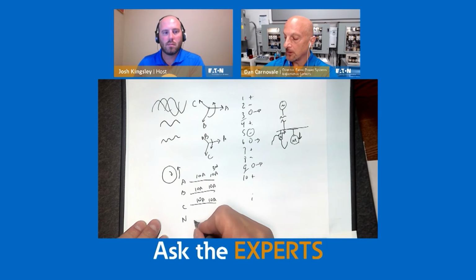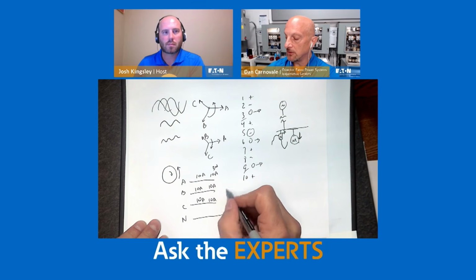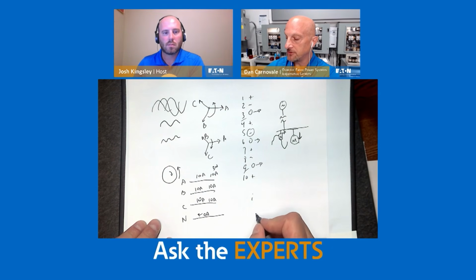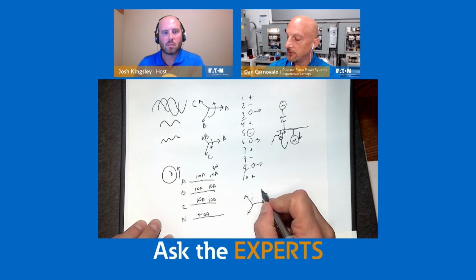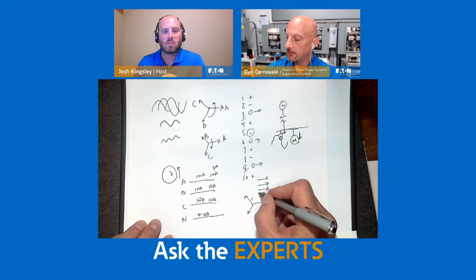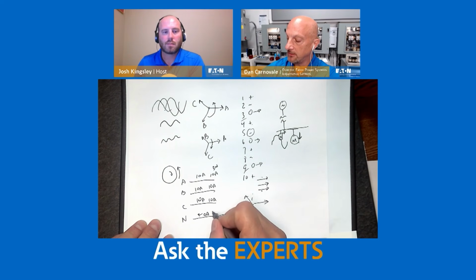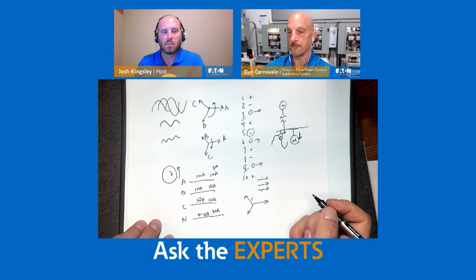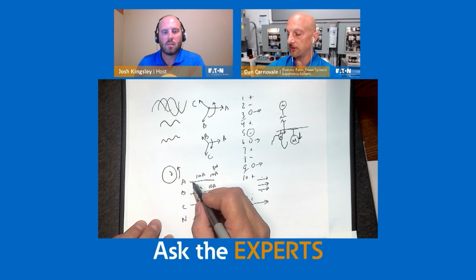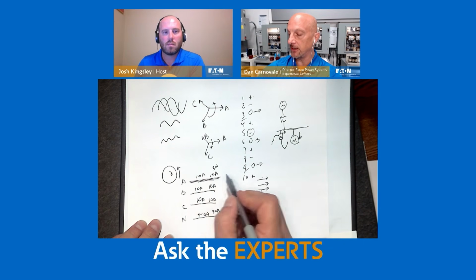multiples of the third. So third, ninth; sixth isn't usually very common. But anyway, what we would have on the neutral out here is 0 amps of 60 hertz. As we mentioned before, 60 hertz A, B, C adds up to 0. But the third harmonics, A, B, C, 10 plus 10 plus 10, is going to add up to 30 amps on the neutral.